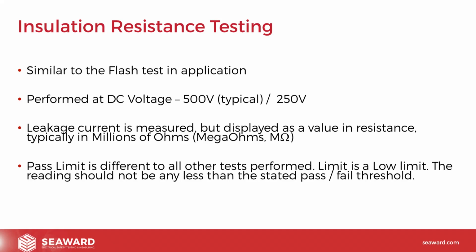And that's just due to the relationship between current and resistance. As the current increases, resistance will decrease. So because we're looking for a low amount of leakage current, conversely what we're also looking for is a high level of resistance. So typically the resistance we're reading will be measured up in megaohms, millions of ohms. And as I said before, we're looking for a higher than reading when we're performing the test. So any limit that we set is typically a floor limit.